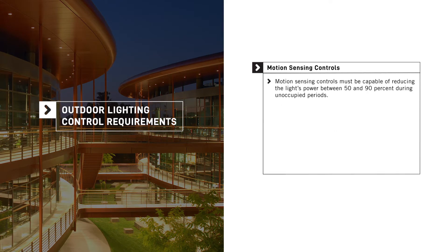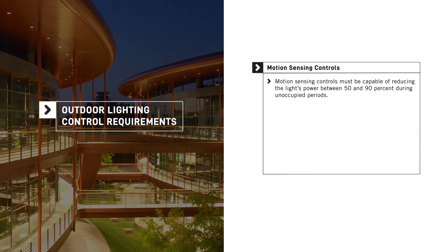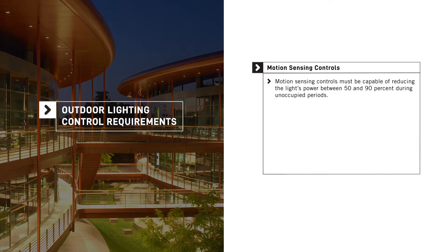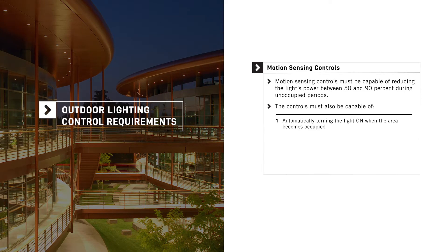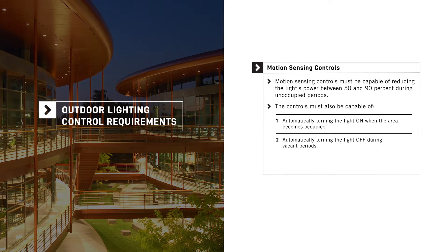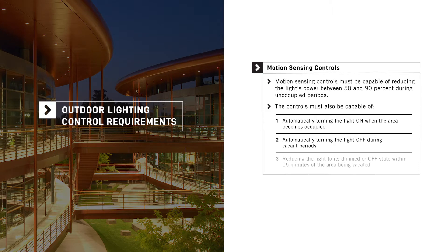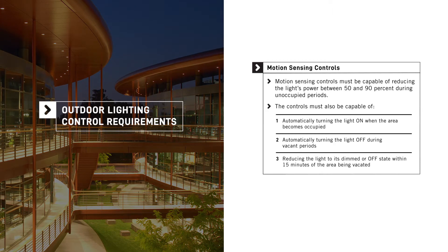Motion sensing controls must be capable of reducing the light's power between 50 and 90 percent during unoccupied periods, including those that occur during business hours. The motion sensing controls must also be capable of automatically turning the light on when the area becomes occupied, automatically turning the light off during vacant periods, and reducing the light to its dimmed or off state within 15 minutes of the area being vacated.